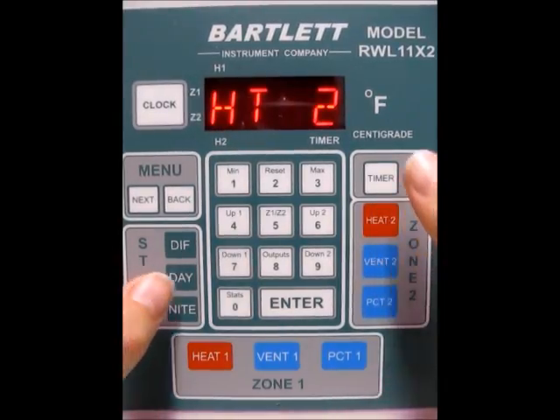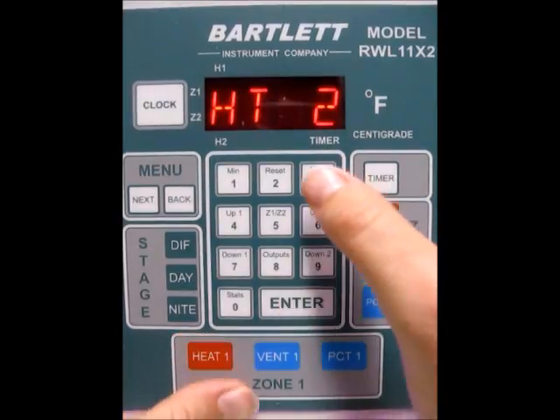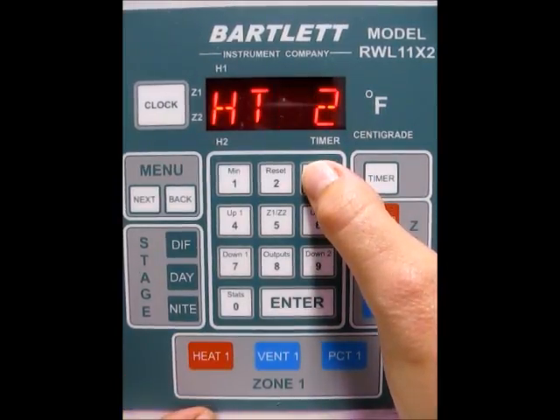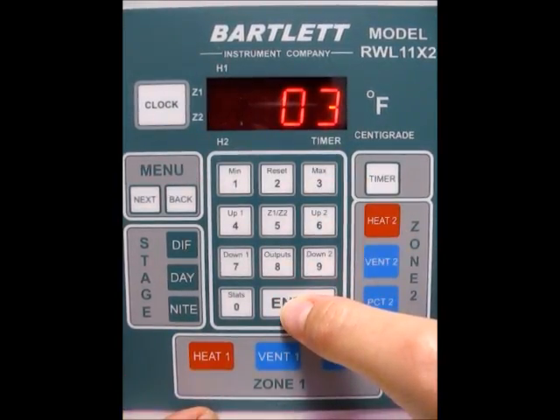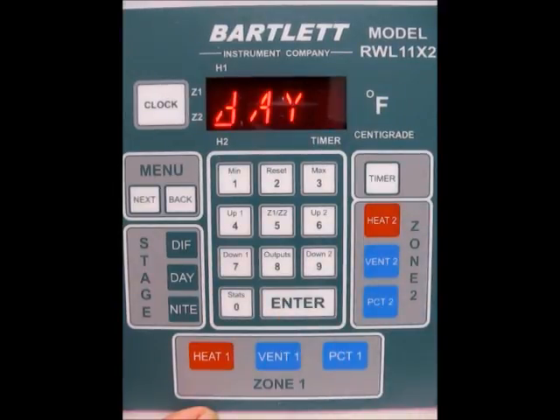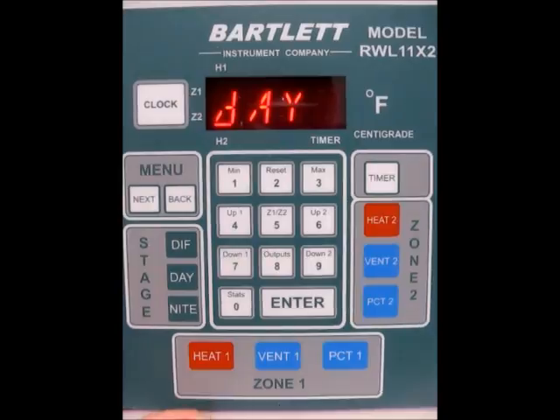So now the same goes for Heat 2. We want to make sure that's at Auto. We're going to program a step size of 3 for Heat 2. And press Enter. And now, again, our output temperature for Heat 2. Now that would be 72 degrees because our target is 75. And that means it will come on at 71 and it will shut off at 73 degrees.